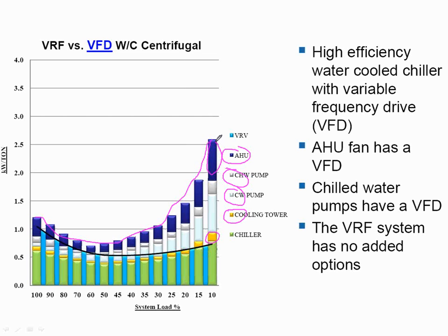And chill water is not a bad way to move energy around a building. It's a really good way, like we said earlier. It's just not quite as good as refrigerant in moving it around. So I think when you look at it that way, you'll see VRF could beat the chilled water systems, even the water-cooled systems, water-cooled chiller systems in many cases.